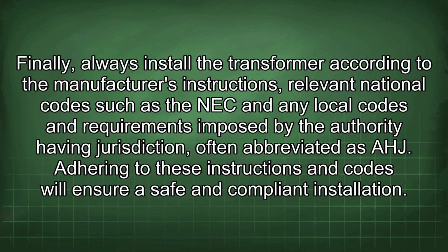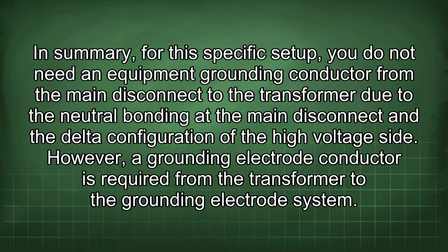Finally, always install the transformer according to the manufacturer's instructions, relevant national codes such as the NEC, and any local codes and requirements imposed by the authority having jurisdiction, often abbreviated as AHJ. Adhering to these instructions and codes will ensure a safe and compliant installation. In summary, for this specific setup, you do not need an equipment grounding conductor from the main disconnect to the transformer due to the neutral bonding at the main disconnect and the delta configuration of the high voltage side.